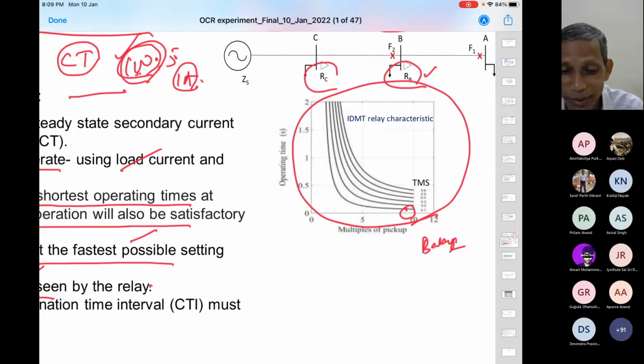But there is a problem with that. If you take curves arbitrarily, even if you satisfy the coordination for the same fault current level, taking an upper curve makes the operating time more. Then you have to take a further upper curve, and the operating time becomes more and more.